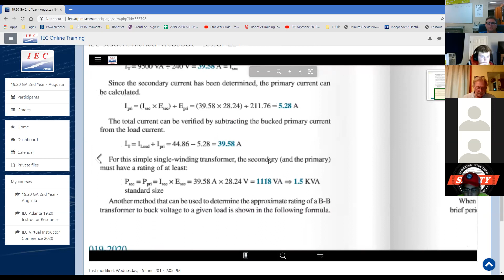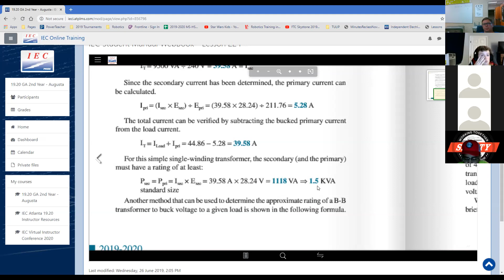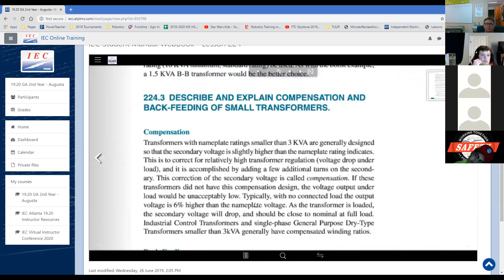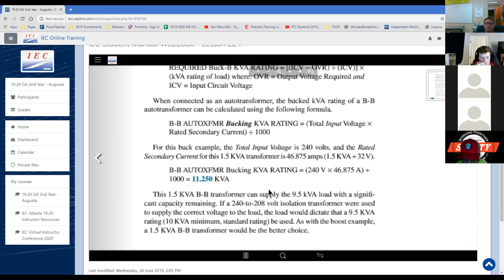So again, why? A simple single winding transformer, the secondary and primary must have a rating of at least 1118 VA, so it needs to at least be a 1.5 kVA. Okay. So, long story short, this 1.5 kVA buck boost can supply the 9.5 kVA load, still with capacity remaining. If the 240 to 208 volt isolation transformer were used to supply the correct voltage, the load would dictate that the 9.5 kVA rating would have to be a 10 kVA minimum. Again, this would be a better choice. It'd be cheaper than using that bigger transformer. Saving money, man. Making it work.